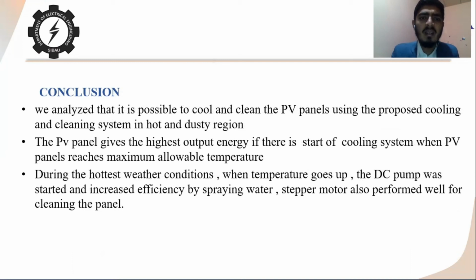We analyzed that it is possible to cool and clean the PV panels by using the proposed cooling and cleaning system in hot and dusty regions. The PV panel gives the highest output energy if the cooling system starts when the PV panel reaches maximum allowable temperature. During the hottest weather conditions, when temperature goes up, the DC pump was started and increased the efficiency by spraying the water. The stepper motor also performed well for cleaning of the PV panel.